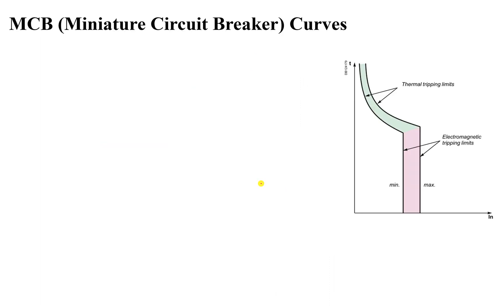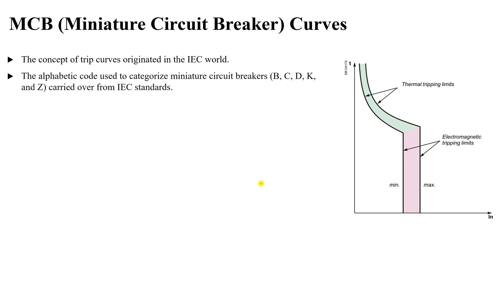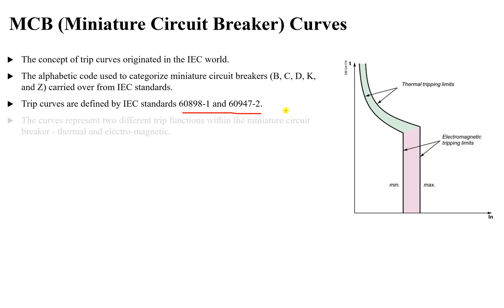Let's start by learning about the miniature circuit breaker curves, or the trip curves inside a circuit breaker. This concept comes from the IEC standard, which defines curves for different types of breakers. There is an alphabetic code to categorize miniature circuit breakers: B, C, D, K, and Z, all coming from IEC standards. These trip curves are defined by the IEC standards.